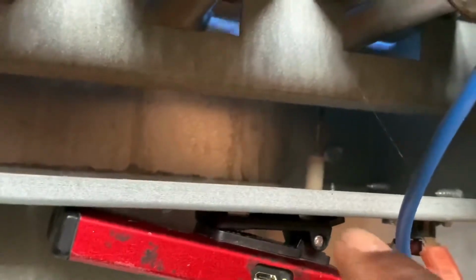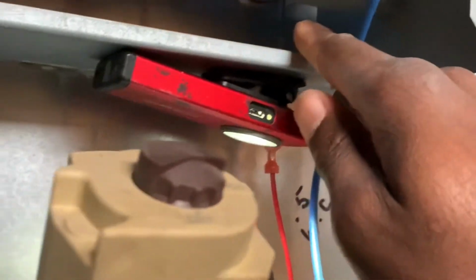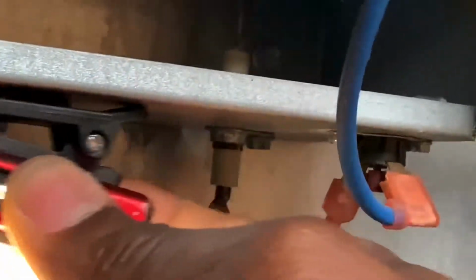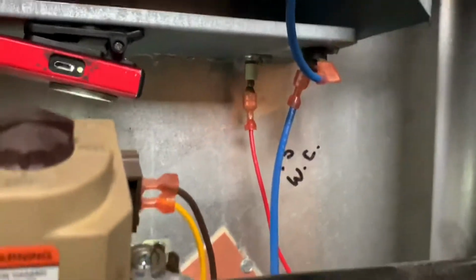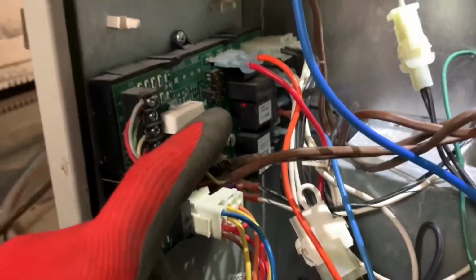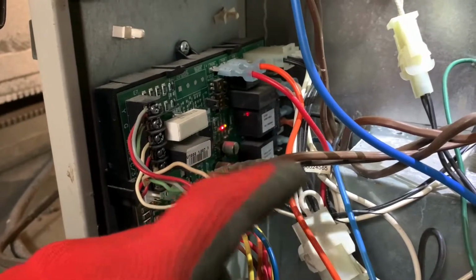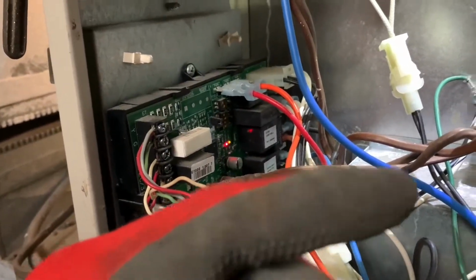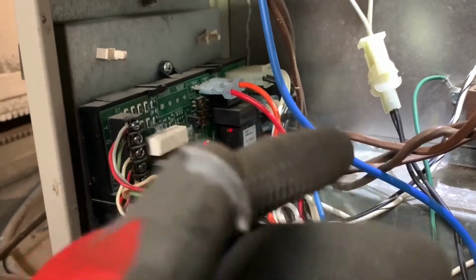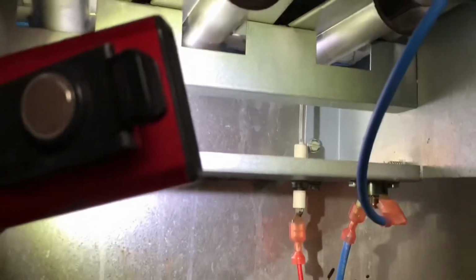Okay, so you can see the furnace lights up right now, and everything is good. Here is your flame sensor right there. There's a flame sensor over here. Let me get my light out of the way. Okay, so how the board usually tells there is a flame in the furnace, how it does it is basically it sends a current or voltage draw through the cable here and up through the sensor, through the actual flame.